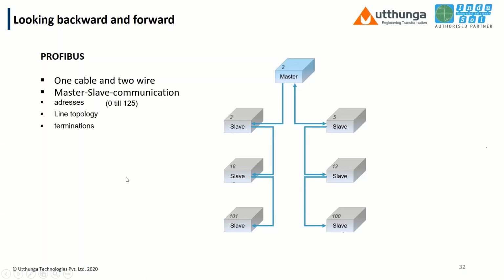101 and 100. You can see 101 and 100. Why is termination important in the network? Because Profibus cable impedance is 150 ohms. The Profibus connector has 3 resistors inside it, put in parallel and in series, so it will give an output of 175 ohms. So it will resist the energy flow.